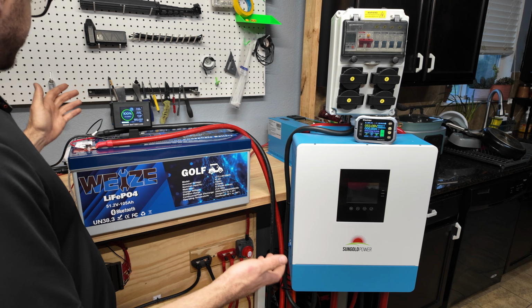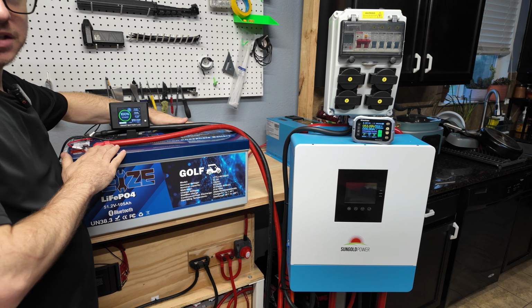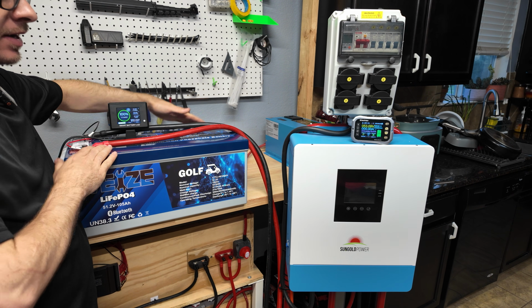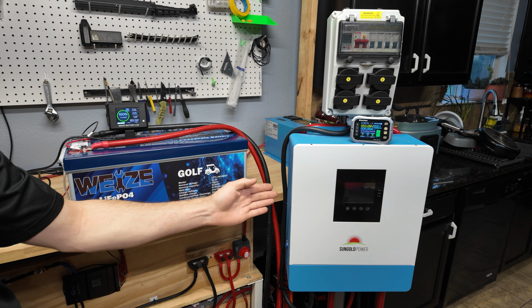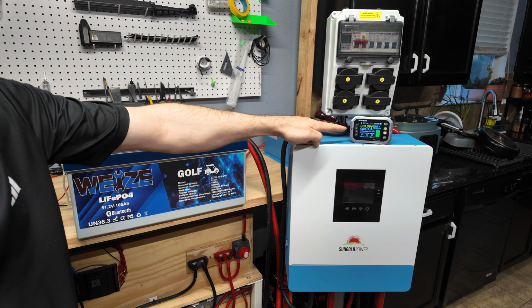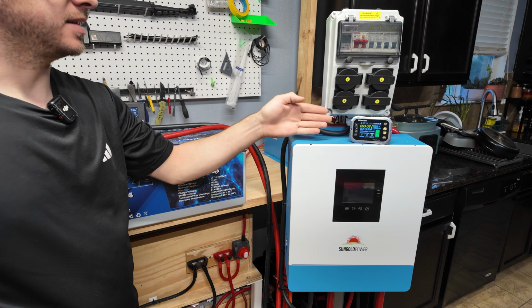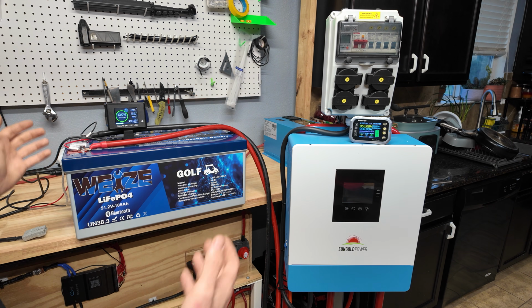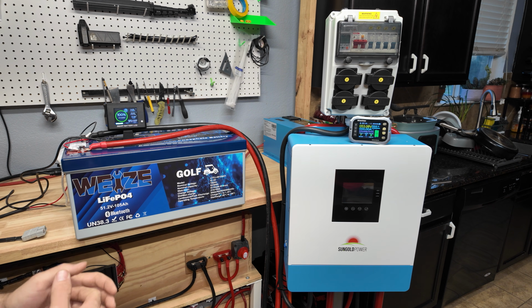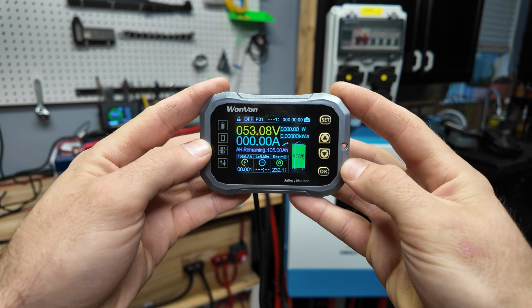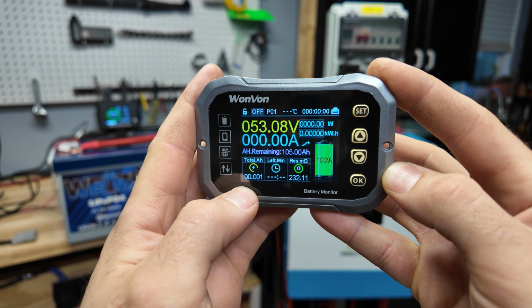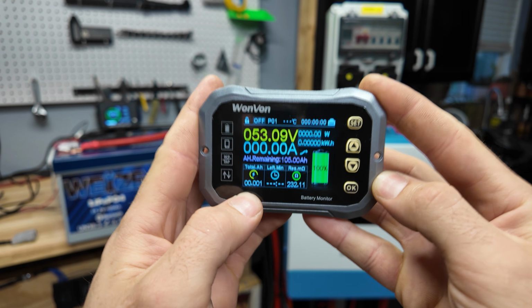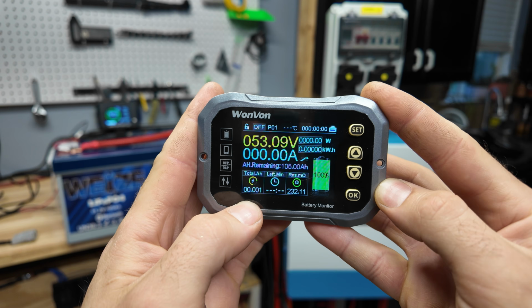Here's a very simple setup I put together to capacity test our WEIZE golf cart battery. We have a SunGold Power pure sine wave inverter connected to the battery through a current shunt, so we can read exactly how many amp hours the battery will give us. We're going to put a 0.2C load on the battery, a little over 20 amps. The current shunt is reset, and the total amp hours will be displayed right here. Once the battery is completely discharged, we'll get our final number.